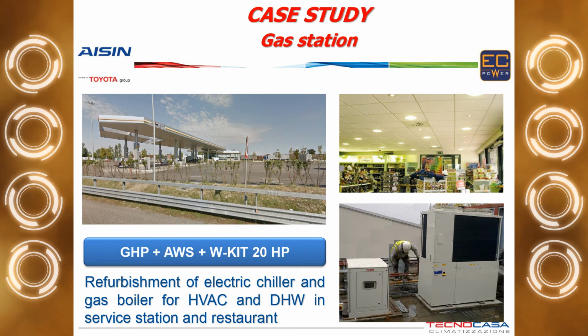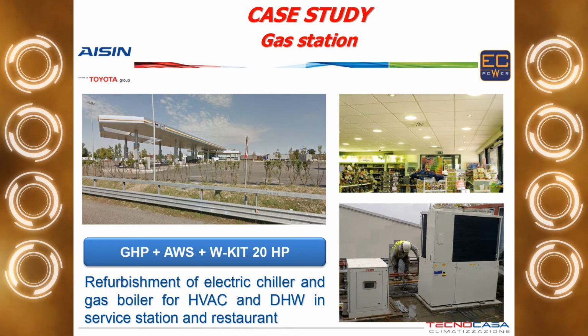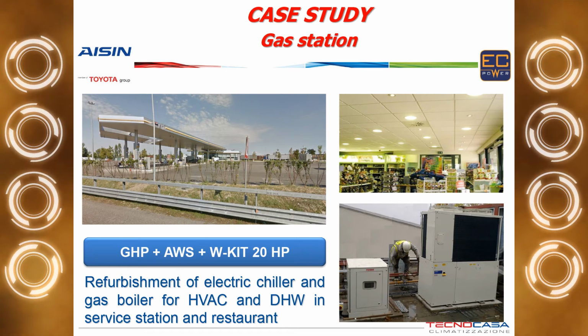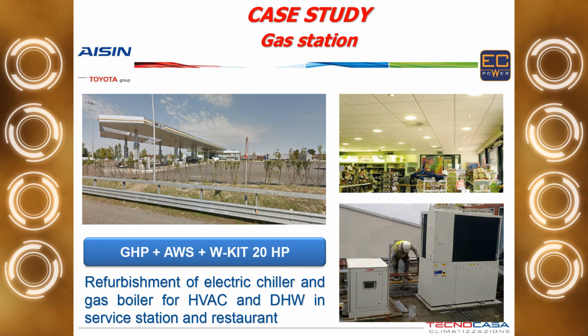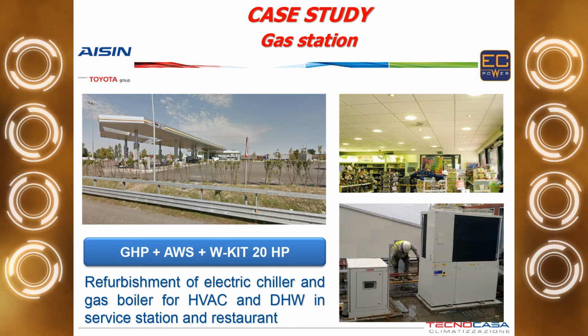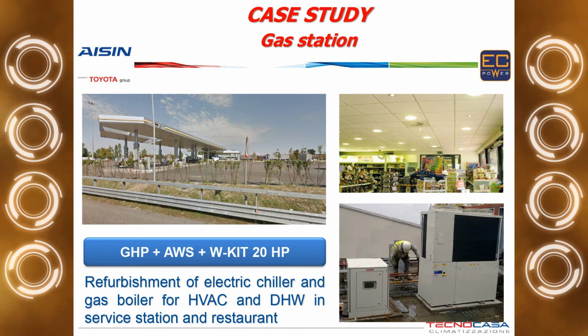This unit is 20 horsepower, so it means 50 kilowatts cooling, 60 kilowatts heating, and it's air to water. The cooling heating is for the restaurant and for the shop of the gas station, and also for the production of domestic hot water, because there is a truck stop on the other side, and they have showers and they have facilities for truck drivers. So what I'm showing you is a running cost comparison. This is, of course, based on the price this customer is paying for the operation of the system, and it's based with the old system which was here, which was made with a gas boiler and an electric chiller.